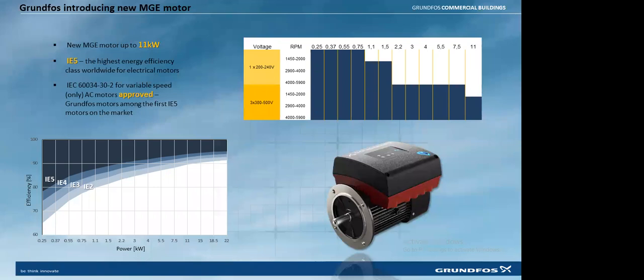From our general observation, most of our water supply applications fall at 11 kilowatt and below. Even if you talk about a water transfer application, any feed pump application, or a high pressure pump in an RO plant, or a hydropneumatic system, all the pumps will fall below 11 kilowatt, unless it is a very huge campus or a township project. So up to 11 kilowatt, we now have our IE5 motors. Of course, we are in the process of developing IE5 motors for higher kilowatt ratings too, which will support us more for our air conditioning applications too.